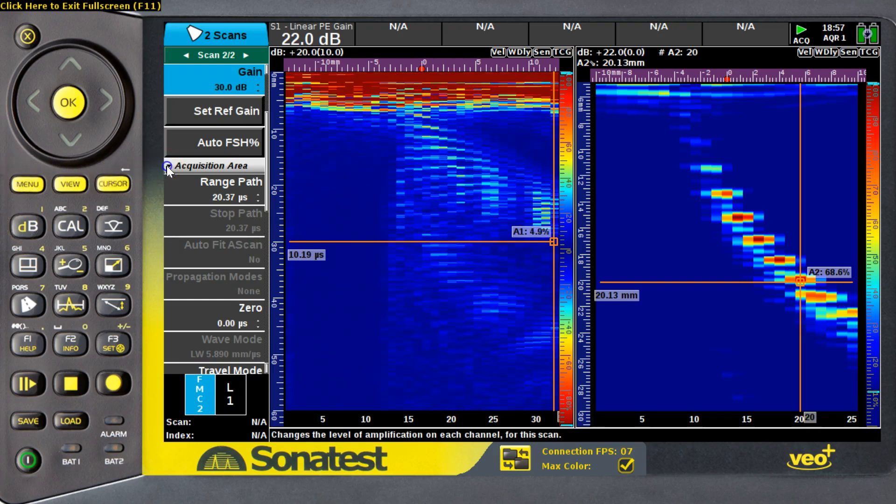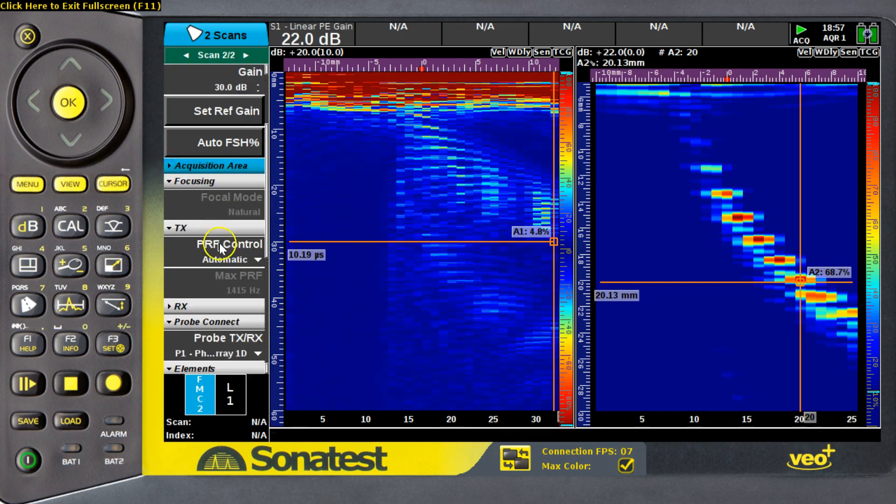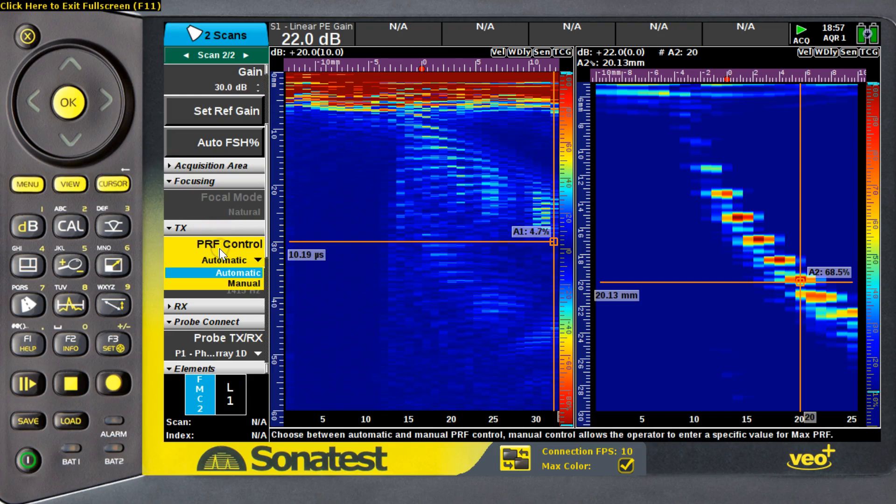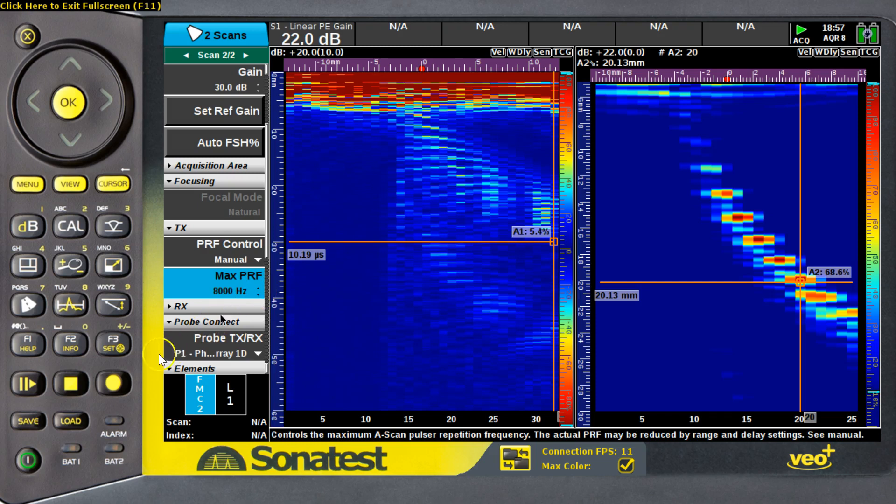Using a similar dB or gain, we can see that the FMC scan doesn't give much information like a Phased Array scan. However, with a few manipulations to increase the speed, I will be able to record that scan on my instrument.